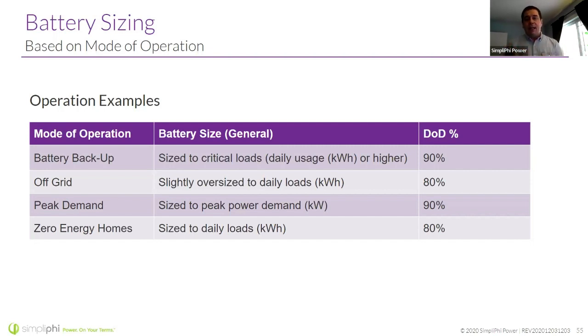If you're cycling more than 80% in an off-grid situation, you may be looking at replacing the bank after the warranty period. Similarly, if you're doing that peak shaving that we showed you up front, where you're only really cycling the top demand off of your usage, you might be able to have a deeper depth of discharge because you're not using the battery as frequently, or you may not even be taking it down to that depth of discharge. Your demand cycling might be just taking the top 10 or 15% off the battery. And similarly, for a zero energy home, or truly a time of use arbitrage kind of setup where you are cycling that battery all the way every day, again, we'd recommend 80%. It gives you the peace of mind that the battery will give you that 10-year warranty, but that it'll also continue after that.